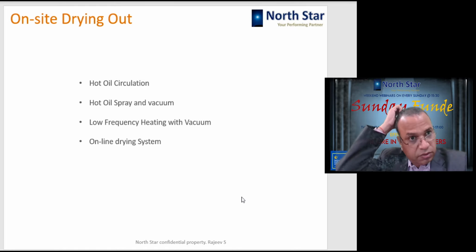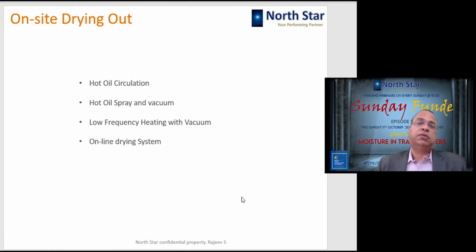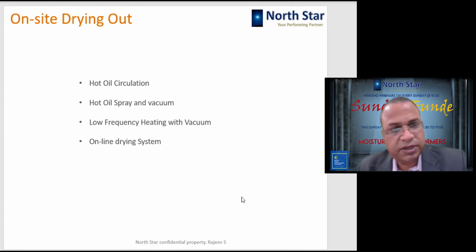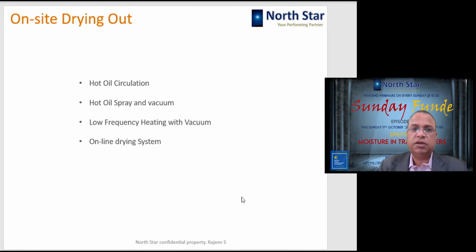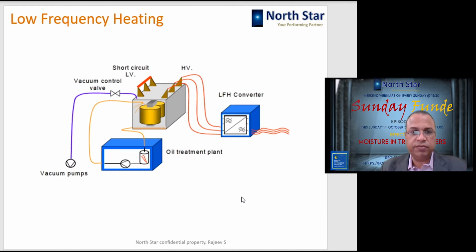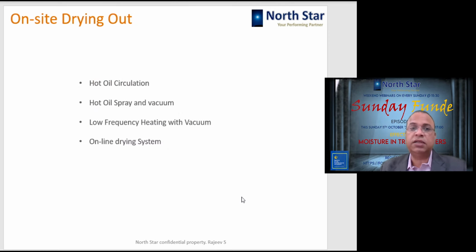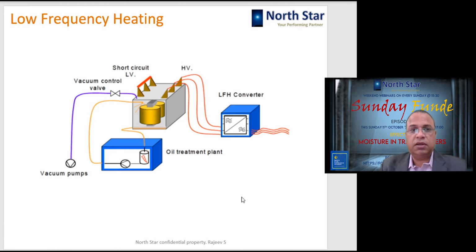Okay, now coming to drying out of the transformers on site, there are several methods. I am not going into the detail of these methods because it is slightly out of context today. I am going to explain only two methods, and that too very briefly. One is low frequency heating with vacuum, and the second is online drying systems. Low frequency heating is a comparatively newer technology as far as transformer drying is concerned, and this is superior to the other two processes which we talked about, hot oil circulation and hot oil spray and vacuum.